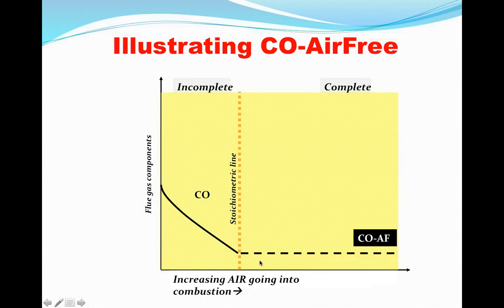If we could somehow remove the impact of the diluting oxygen and look straight back to the intersection where CO comes over the stoichiometric line, to the point where there's 0 oxygen present, that is the CO-AirFree number. The CO-AirFree number then does not change as you increase the oxygen level. So it provides more of a system fingerprint as to how it's running for the absolute amount of CO there.